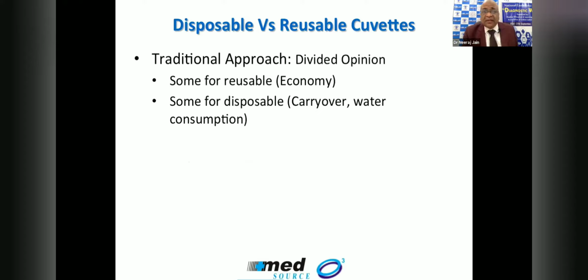And then another thing is whether we should use disposable cuvettes or reusable cuvettes. If we are using reusable cuvettes, they are economically good, but then we have to see that they are washed properly, otherwise there may be some problem. If we are using disposable ones, we can take care of the carryover or water consumption problem, because if the machine is washing those cuvettes on board, it will increase the cost.